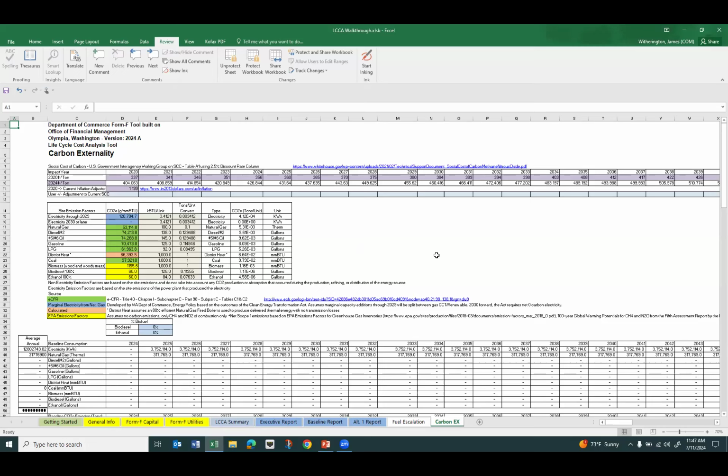I want to look back at the standard and make sure there's not any specific language in Annex X that would prevent you from doing that for single measures. It's probably not specifically called out in there, but we'll see if we can make an interpretation. Luke, to add on to that, there is the exception, and I can't quite quote the numbers like you can, but whenever you've developed a list of EEMs and the building owner determines that they're going to implement all EEMs, I believe that exception does allow you to omit Form F because you've implemented all identified EEMs. Yes, that's a good point, James. Let's just confirm that that is still applicable when you've eliminated EEMs by simple payback, because it might be specific to all EEMs identified by the energy audit prior to the simple payback screening. Okay, so we'll follow up in a published Q&A with that.